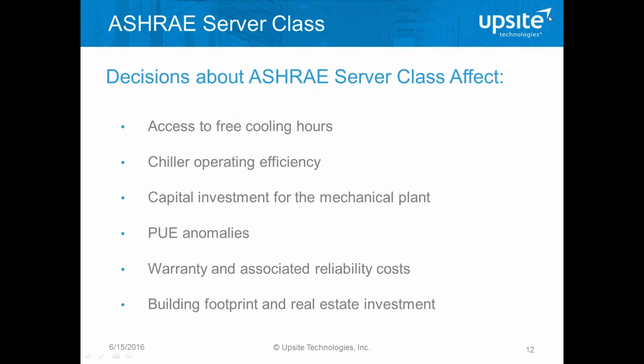But these are important decisions because they will affect the operating temperatures that we're using in the data center, that will directly impact our access to free cooling hours, our chiller operating efficiency. They might even affect the capital investment on, are we even going to need to build a mechanical plant for the data center? And they can also affect what I call PUE anomalies. And this has to do with when we can reduce the PUE of a data center, but actually increase the overall energy consumption of the data center. This can happen if we're using Class A1 servers, for example, at 86 degrees. You're going to see somewhere around a 40% increase in air demand.